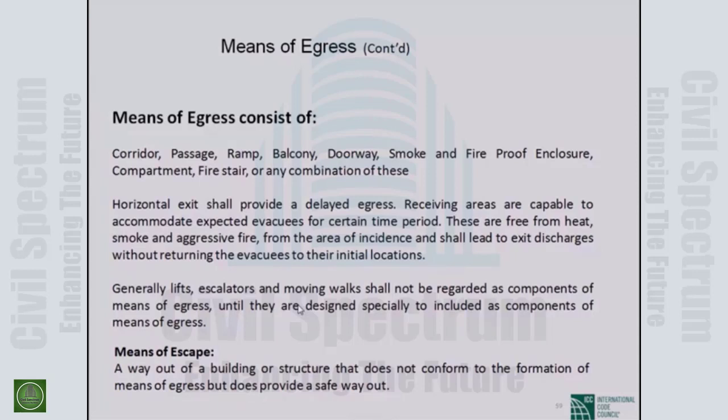Generally, lifts, escalators, and moving walks shall not be regarded as a component of the means of egress. It is not generally, but there are some special cases where they are designed specially to be a component of the means of egress. In that case, the fire lift will be designed such that the fire lift can be used as an exit.